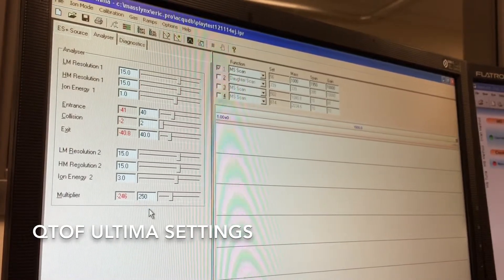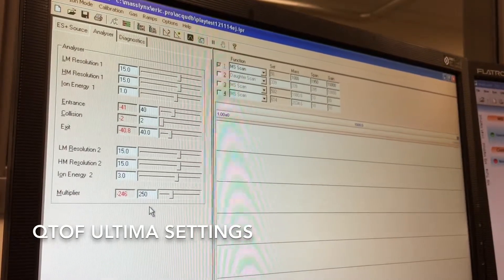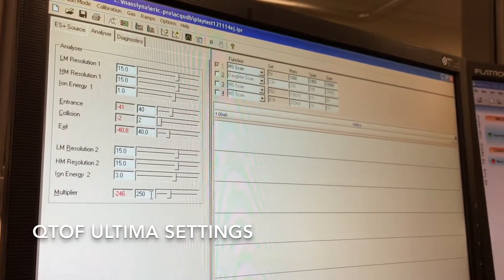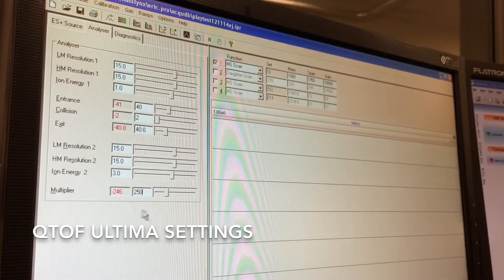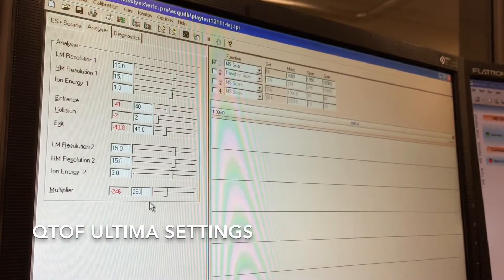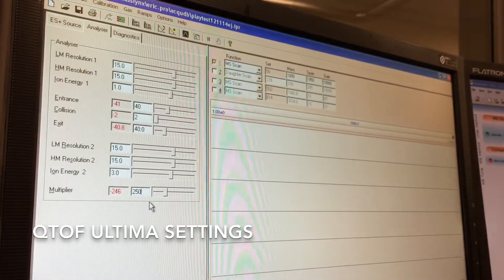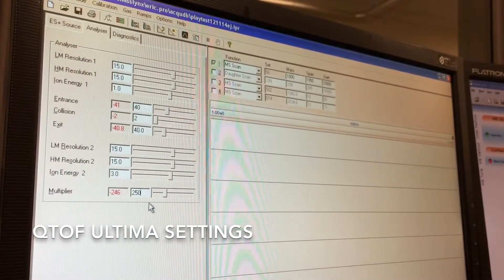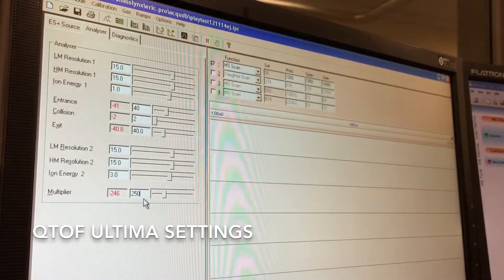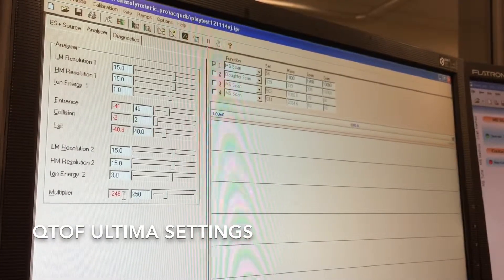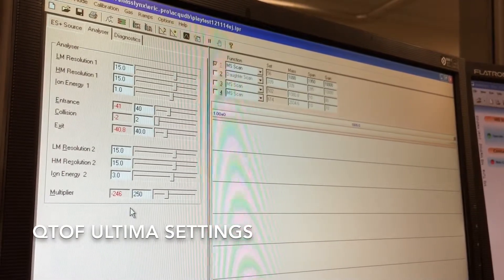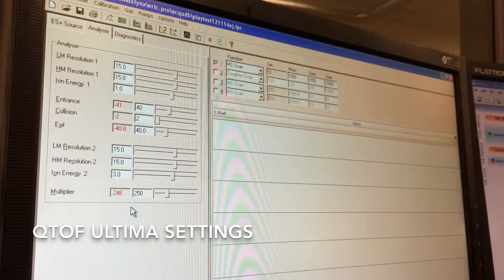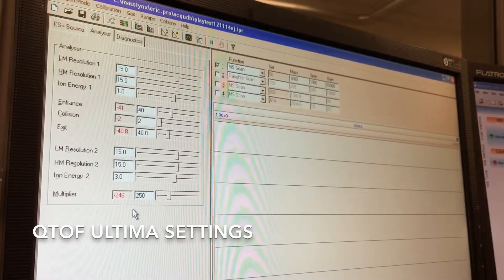The multiplier is the detector. In this case, and in most cases, I have it set to a slightly lower voltage of about 250. And that's largely to get rid of solvent aggregates. However, if you're doing MS-MS modes, you may want to increase this as high as 650, 750, but be aware that your noise will also increase.